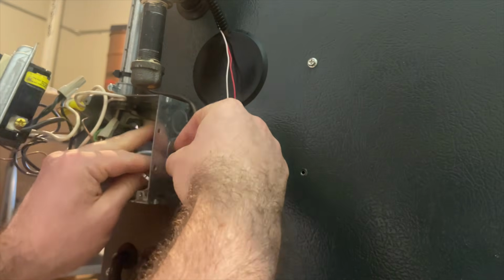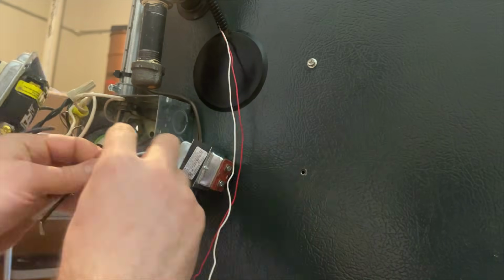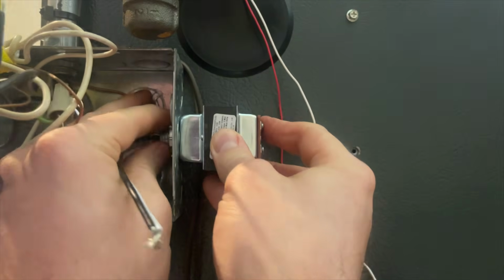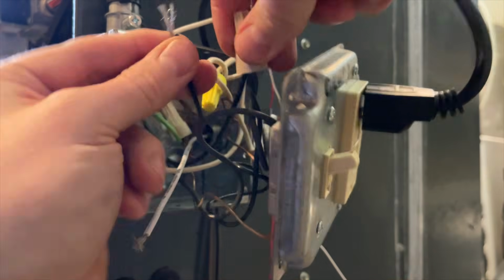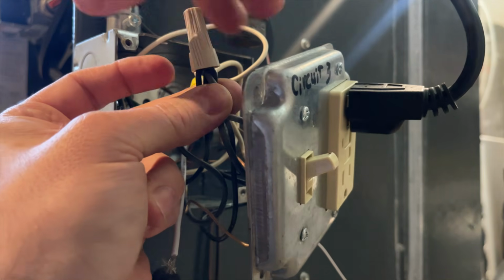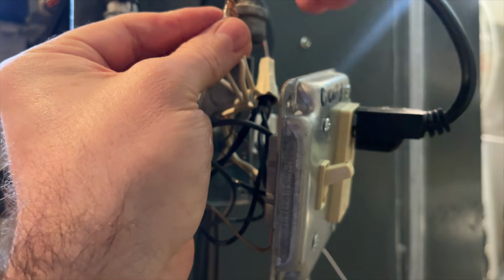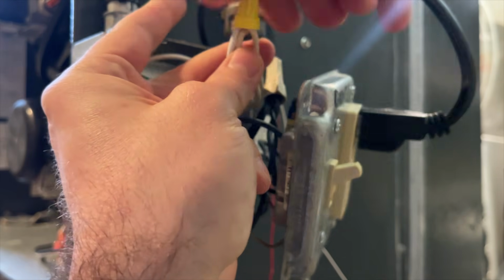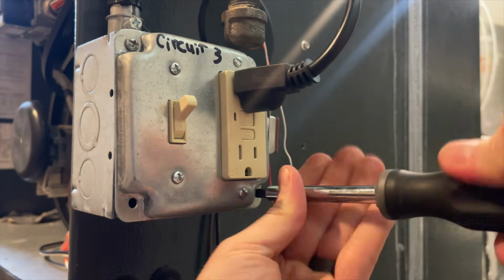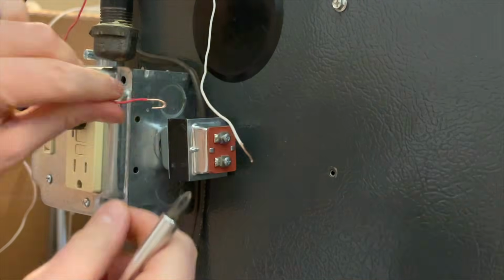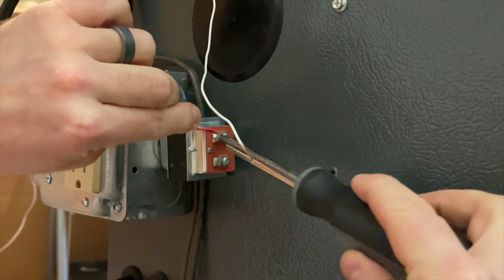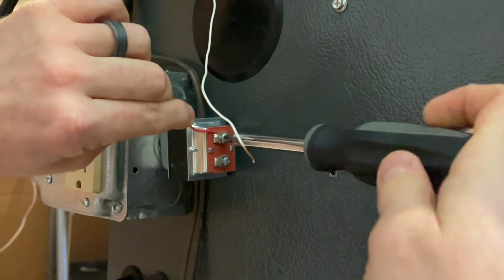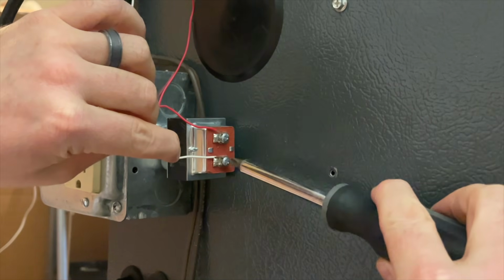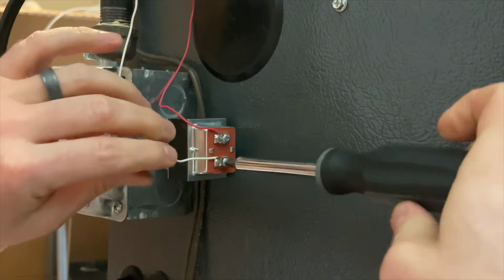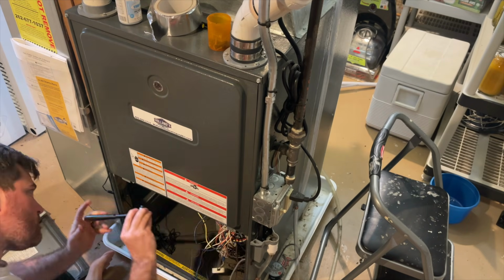First, you need to punch out one of the slots in the electrical box. Insert the transformer and tighten down the nut. Attach the black and white wires to the corresponding wires in the electrical switch area. We want to attach it to the switch which controls the shutoff for the furnace. So with one switch we can shut off the furnace and the humidifier. We're going to attach our red and white wires to the outside of the transformer. Now let's button it all up and see if it's working.